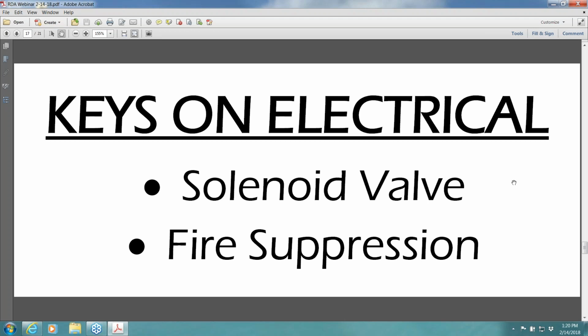The other part of that is fire suppression. There's always an electrical component to fire suppression, because you are tying the fire suppression system into the paint booth controls. Those two things have to be connected. So again, your fire suppression has to receive power.